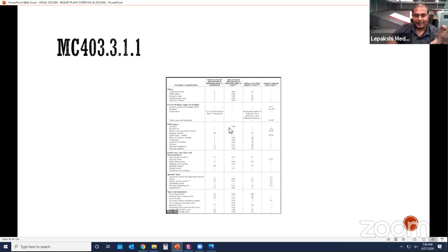which falls under energy code compliance. Now you're providing all that steam, and that has to be distributed. So you will have piping systems, steam supply, condensate return, all of which is hot. The pipe is going to be very hot, while the ambient air surrounding the pipe is at room temperature. So there will be a lot of heat loss, because heat transfer takes place there. You have to minimize that. How are you going to minimize it? You're going to put on insulation. How thick that insulation will be depends upon these codes.